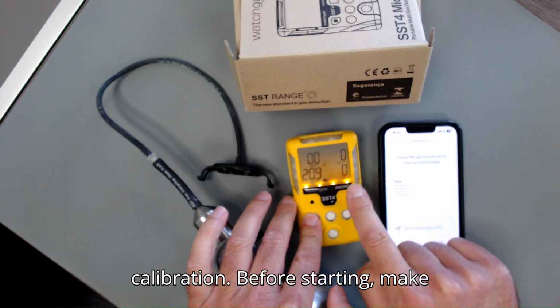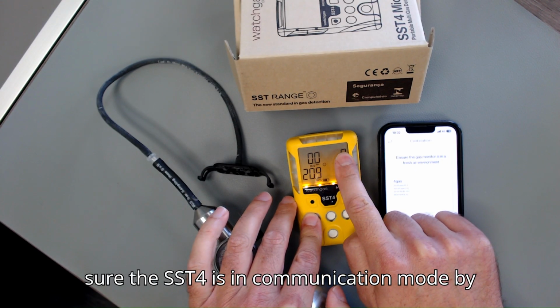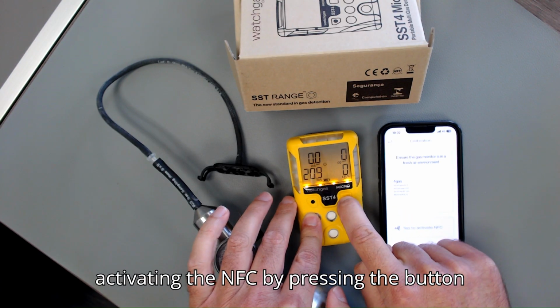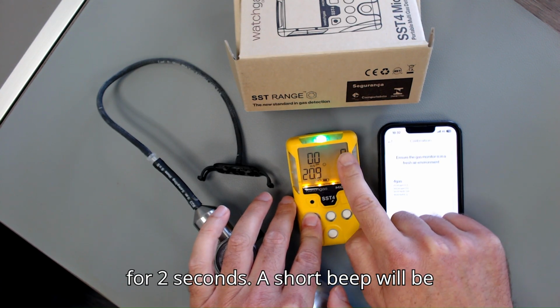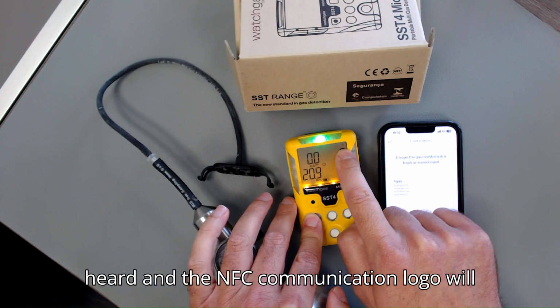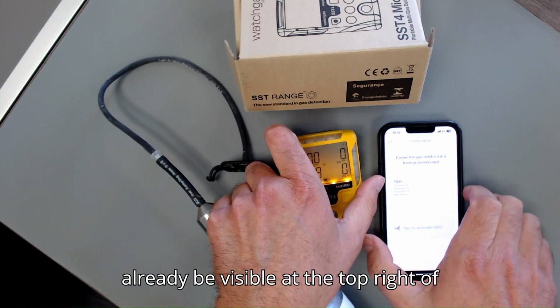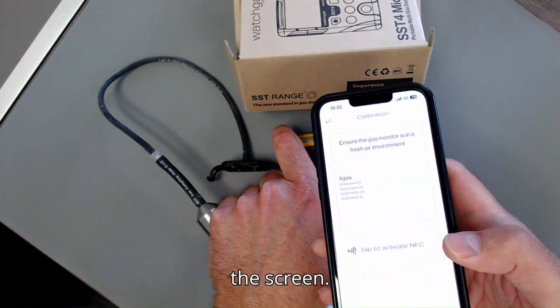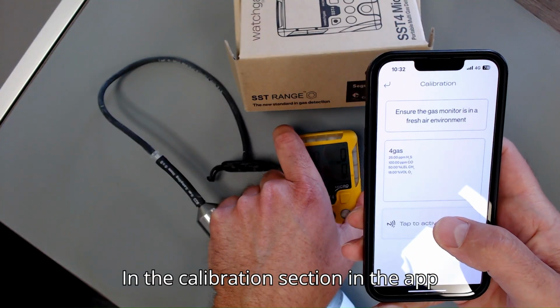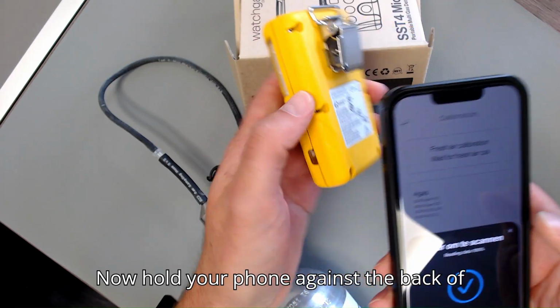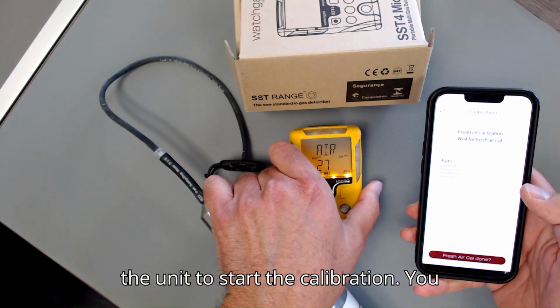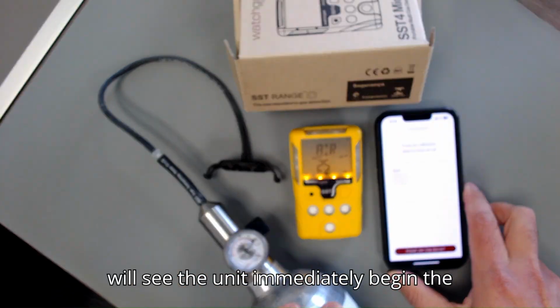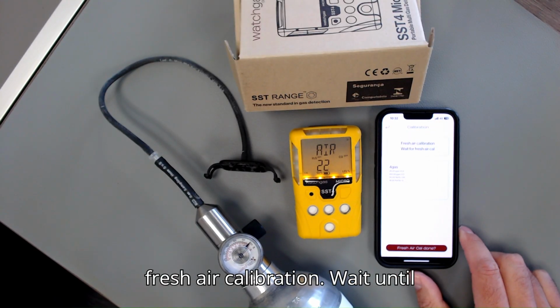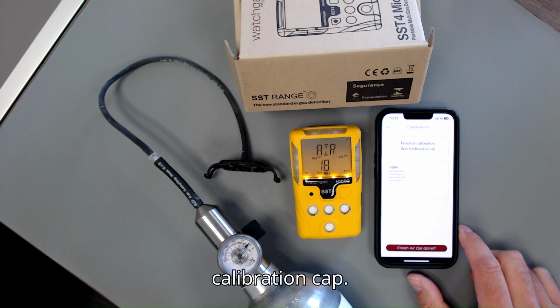Before starting, make sure the SST4 is in communication mode by activating the NFC by pressing the button for 2 seconds. A short beep will be heard and the NFC communication logo will already be visible at the top right of the screen. In the calibration section in the app, press Tap to activate the calibration. Now hold your phone against the back of the unit to start the calibration. You will see the unit immediately begin the fresh air calibration. Wait until this is complete before mounting the calibration cap.